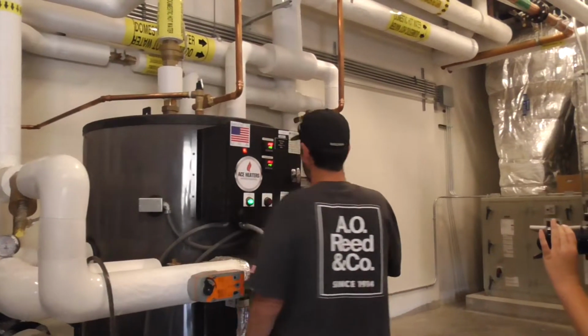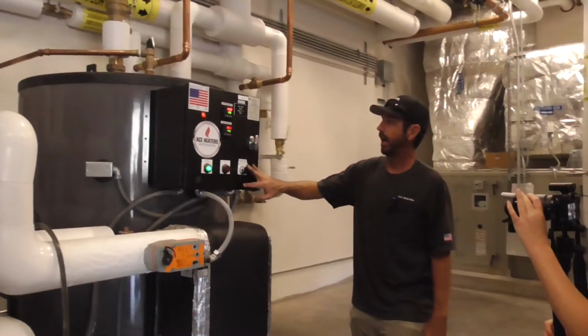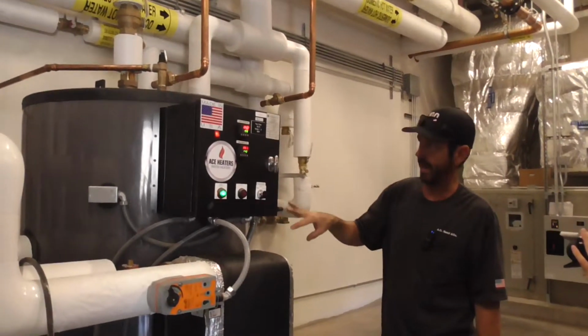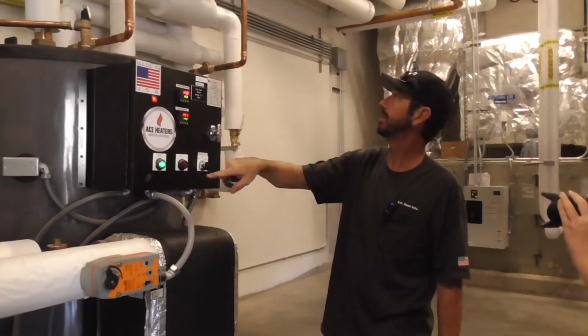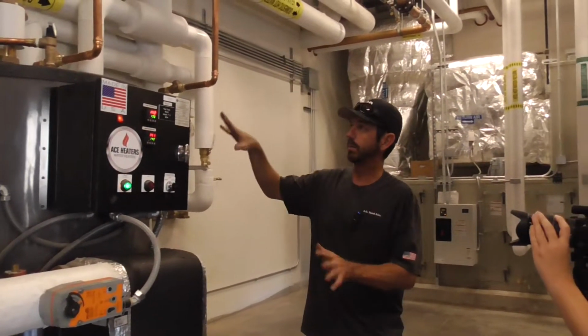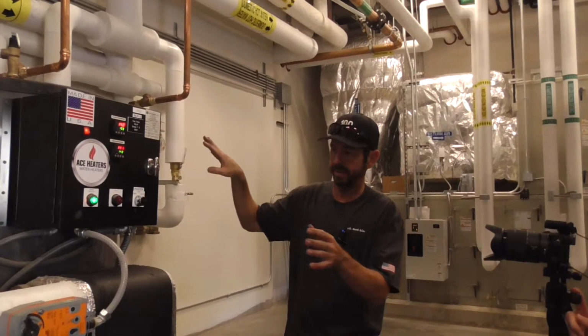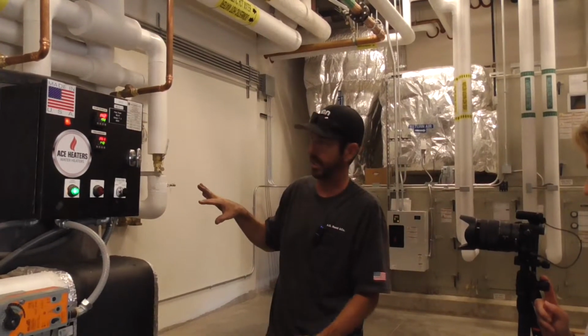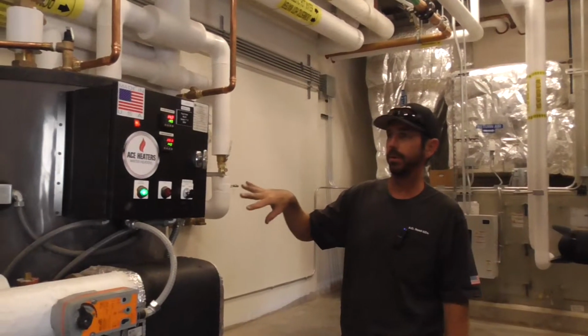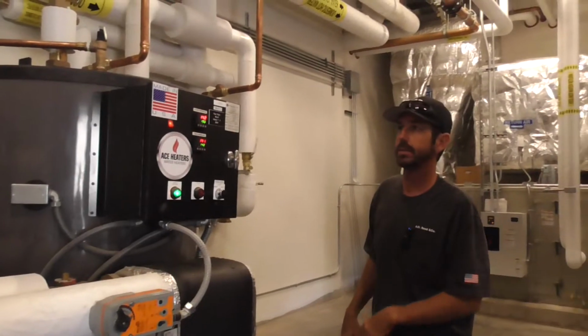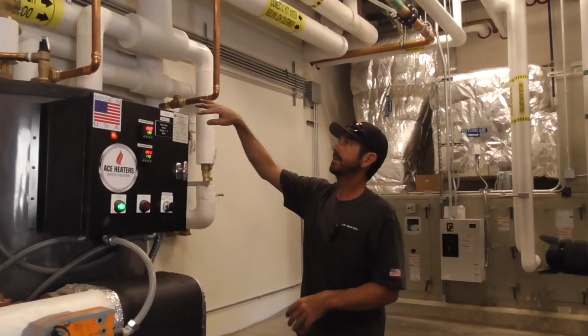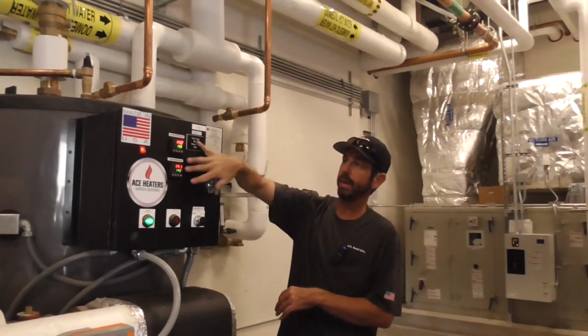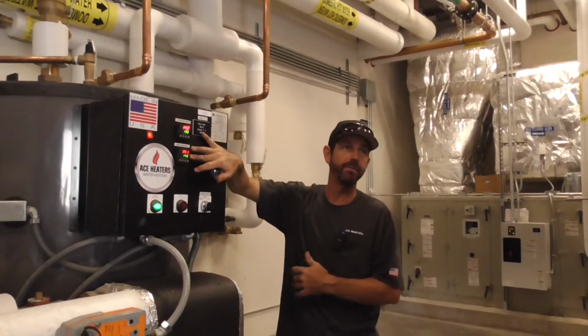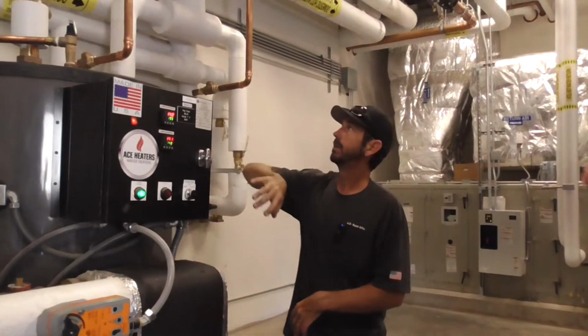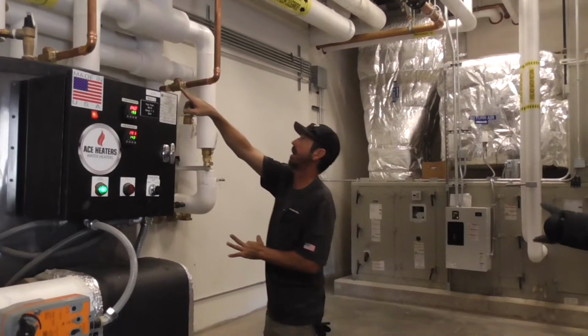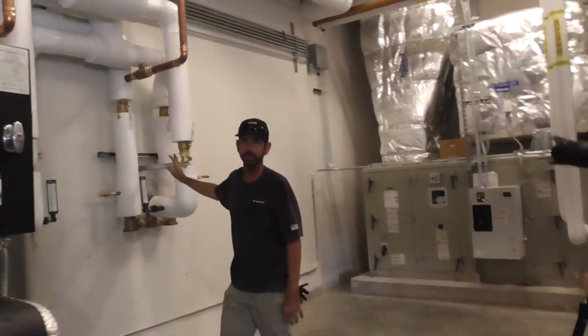Okay, so now leaving, we're in auto, all the controllers powered back on, we didn't shut any valves, the valve is open. Okay, so we can walk away from this now that we've touched it. We've done a visual inspection to make sure everything's good and back in all the appropriate positions. So for domestic hot water leaving, remember we're maintaining 140, so if we send out 140 to the building, we can burn people.